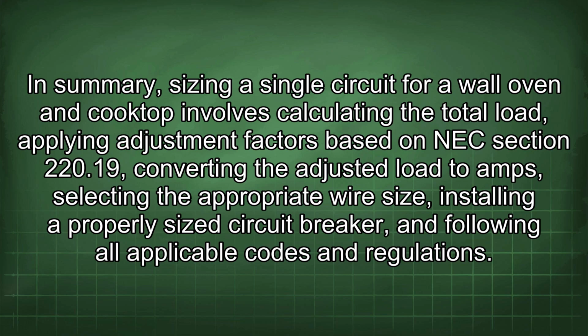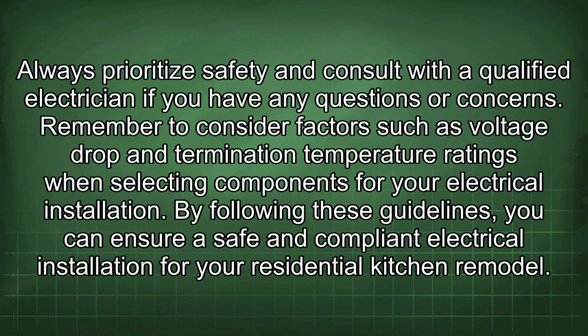In summary, sizing a single circuit for a wall oven and cooktop involves calculating the total load, applying adjustment factors based on NEC section 220.19, converting the adjusted load to amps, selecting the appropriate wire size, installing a properly sized circuit breaker, and following all applicable codes and regulations. Always prioritize safety and consult with a qualified electrician if you have any questions or concerns. Remember to consider factors such as voltage drop and termination temperature ratings when selecting components for your electrical installation. By following these guidelines, you can ensure a safe and compliant electrical installation for your residential kitchen remodel.